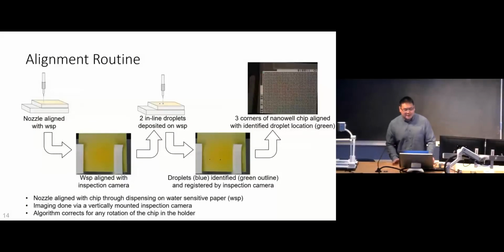The alignment routine is laid out here, which is performed to align the nozzle with the small features of the nanowell chip, which is as small as 500 microns in diameter with a pitch of 542 microns. This routine uses water-sensitive paper placed near the substrate on the carriage. The routine works by first aligning the nozzle with the water-sensitive paper. Then the water-sensitive paper is aligned with a vertically mounted inspection camera we have on our instrument.